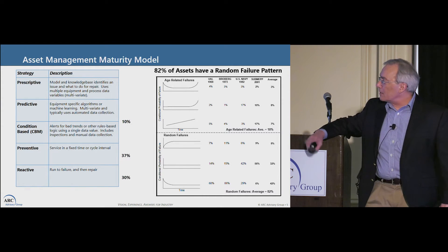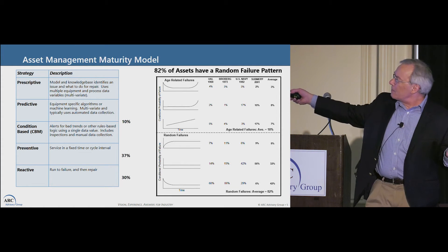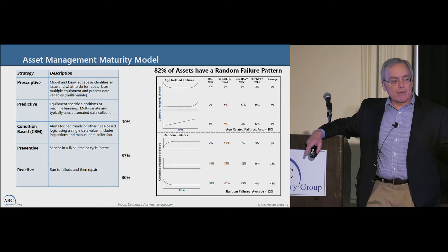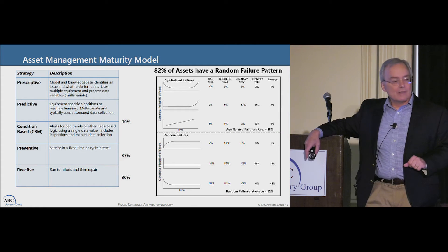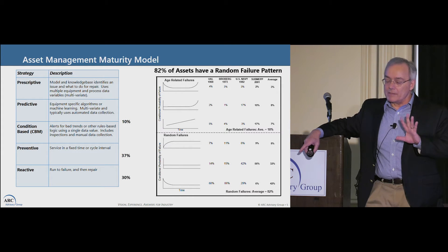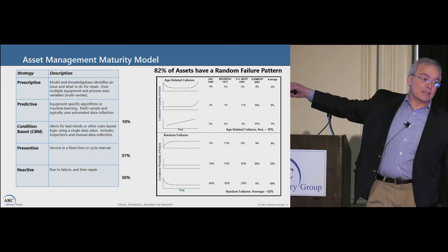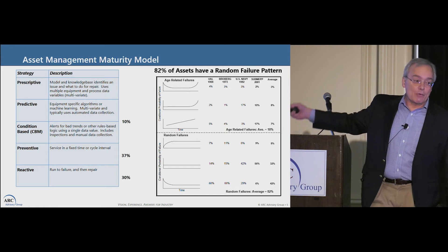The second key point to bring up in this chart is that 82% of assets have a random failure pattern. You're doing preventative maintenance at the point where that curve goes up, but if you have a completely random failure pattern, there is no 'up' on this curve. So preventative maintenance does not apply. There's 82% of your assets where, even if you were to do preventative maintenance, it would be inappropriate.